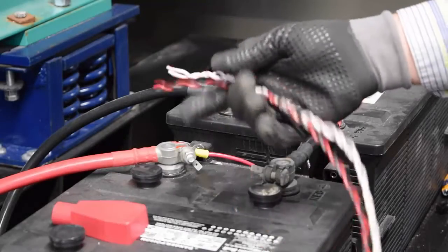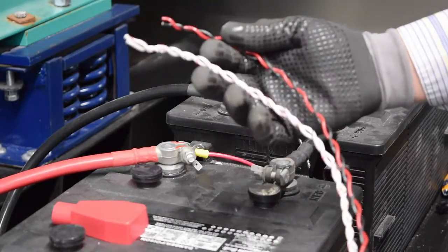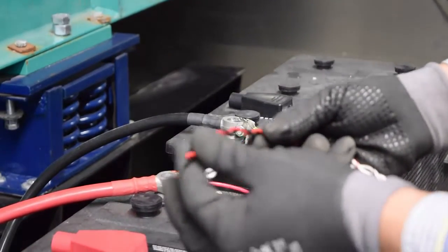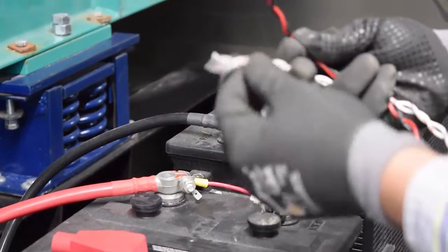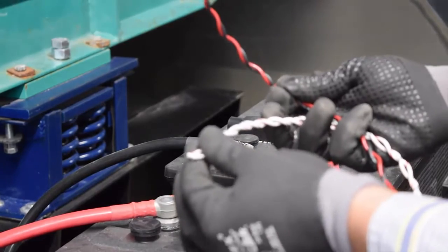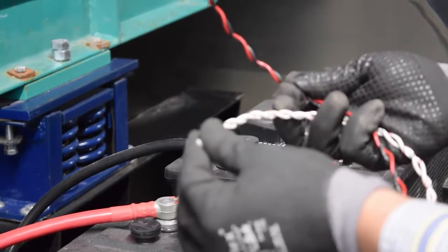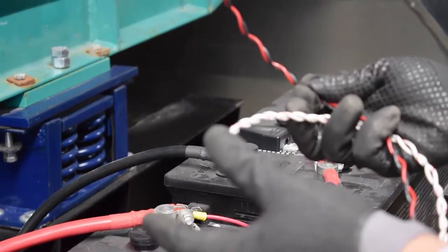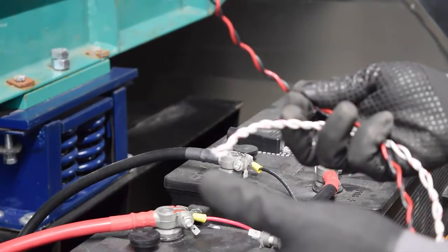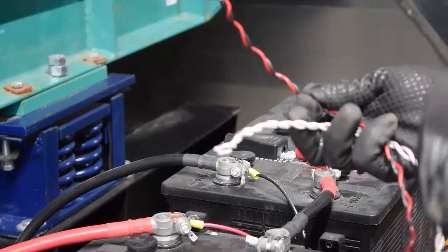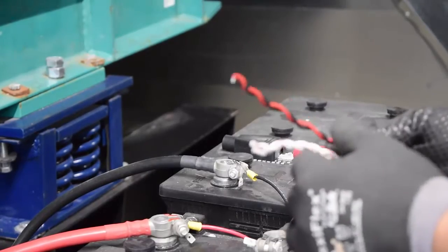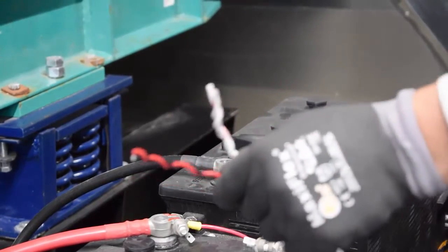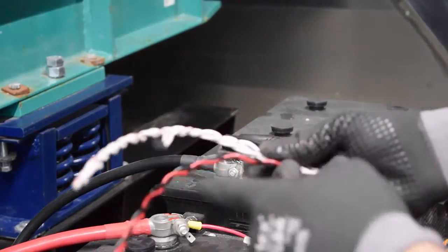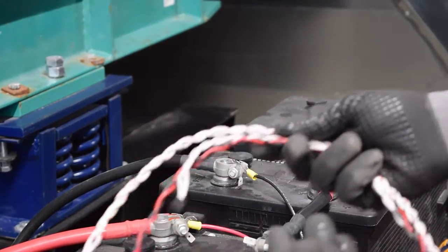Now the cable harness has two twisted pairs of wires, the red and black pair that powers the VTZ module, and the red, white, and black, white pair that's used as impedance sense leads. Optionally, some or all the harnesses also will have a battery unit temperature sensor which has a twisted pair of white wires, such as this one. That's the thermistor.